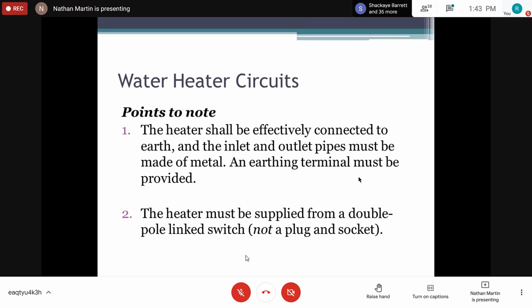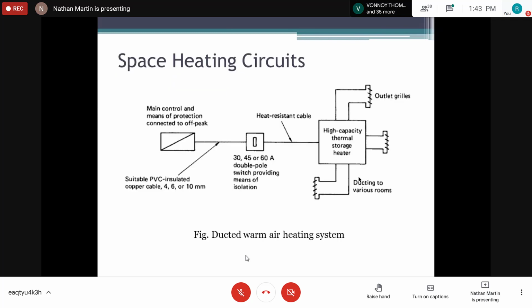You can't use a 220 socket outlet for a fixed appliance such as a water heater. It must be of a switch outlet type, right? A double pole link switch, which can either have a pilot light or be without a pilot light, right? So it doesn't matter if it has the pilot light or not. The pilot light is really for your benefit, to know that when it's lit, there's power to the water heater.